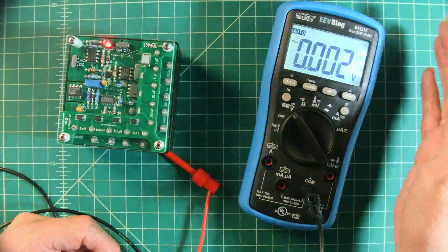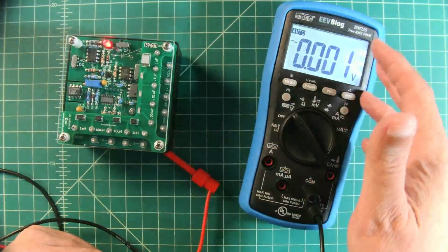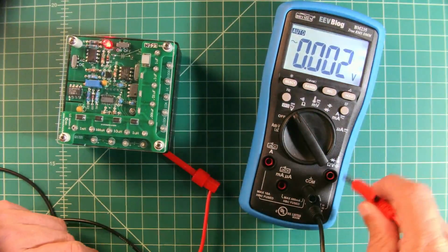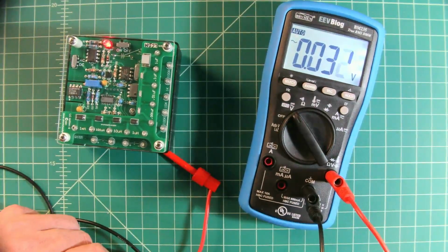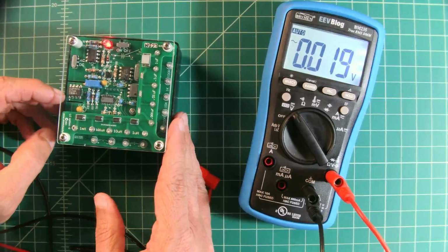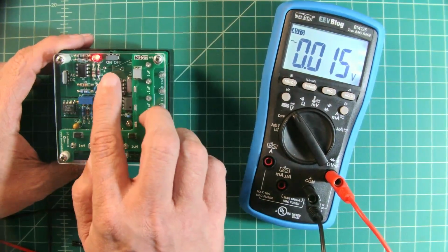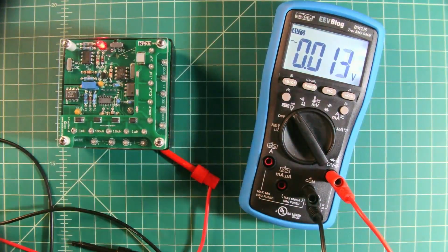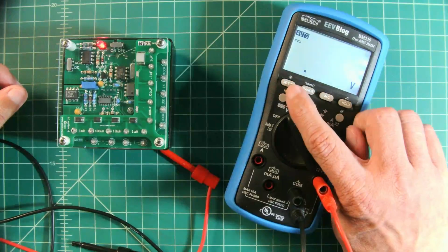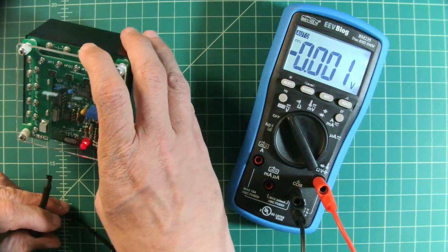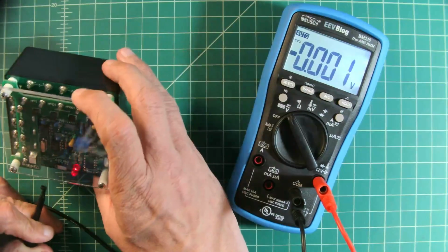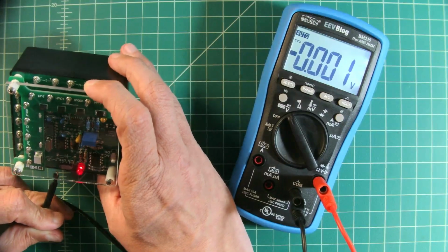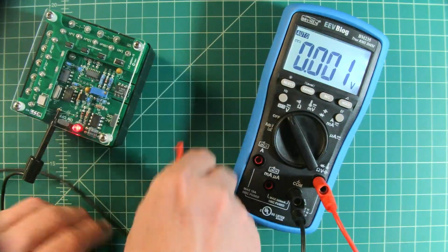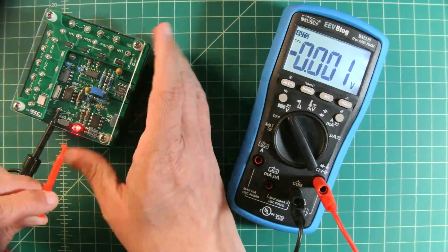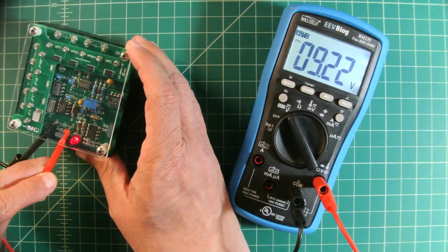The other thing is that we're not testing the accuracy of this meter. We're using this meter to demonstrate the functionality of the DMMCheck Plus. So let's go ahead and hook these up. I think I mentioned it earlier, this runs off of a 9-volt battery. And in here, you can see a positive and a negative terminal. They are for testing your battery. So one of the things I wanted to do was just do a quick test and see how we're doing on the 9-volt battery. I believe they said somewhere around 7 volts is where you would want to think about replacing your battery. But you would do that based off of whatever is in the instruction manual, not what I'm telling you now.